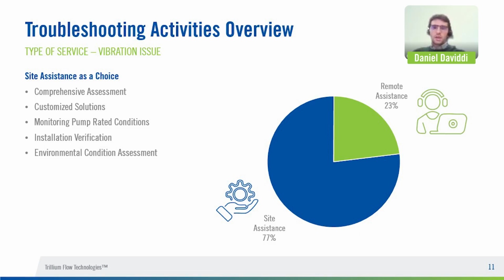We can directly monitor the pump's rated condition and performance in its actual operating environment. On-site presence allows us to verify the correct installation and alignment. And finally, we can assess the environmental conditions that may affect the pump performance. I would like to add that as a globally present company with various service centers, we are able to assist our clients in the field with specialized equipment and skilled personnel.